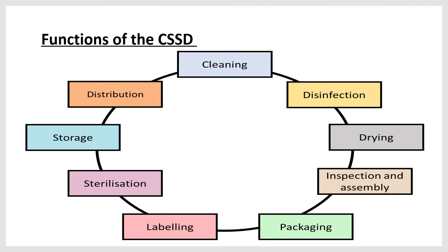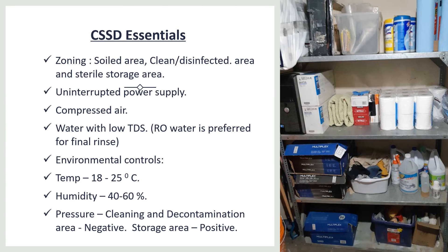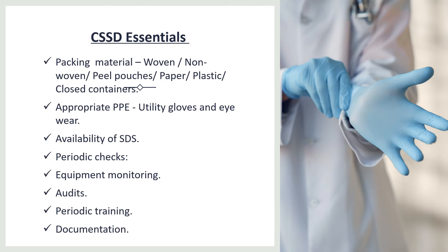The functions of the CSSD include cleaning, disinfection, drying, inspection and assembly, packaging, labeling, sterilization, storage, and distribution. Essential infrastructure includes zoning, uninterrupted power supply, compressed air, water with low total dissolved solids (TDS), and RO water for the final rinse. Environmental controls require temperature of 18 to 25 degrees Celsius, humidity of 40 to 60 percent. Decontamination areas maintain negative pressure ventilation, while storage areas maintain positive pressure. Packaging materials include woven, non-woven, peel pouches, and paper or plastic closed containers. Appropriate PPE includes utility gloves and eye wear, with availability of safety data sheets.